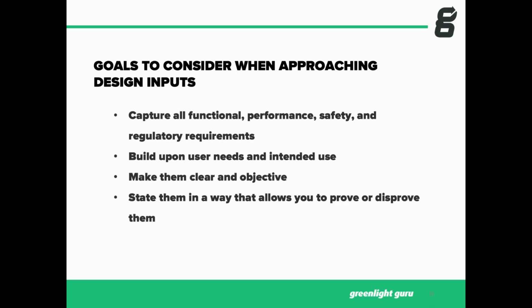Like I said with the waterfall diagram a moment ago, it's really important to build upon those user needs and indications for use. You've got this idea for a product, you've got some problem that you're trying to solve, and you're trying to capture what's important from the patient perspective, from the end user perspective. And remember, from an end user perspective, this doesn't just have to be the doctor or the nurse or the patient. It could be the purchasing person at the hospital. There might be certain things that person has from a user need perspective that are important about the way a product is packaged or the way it's labeled or things of that nature.